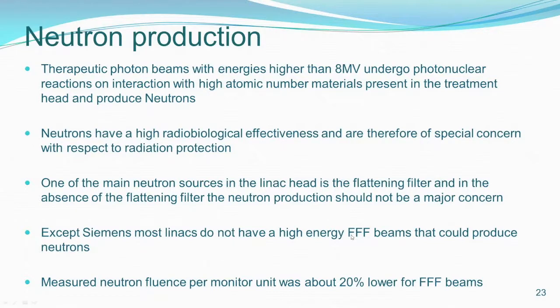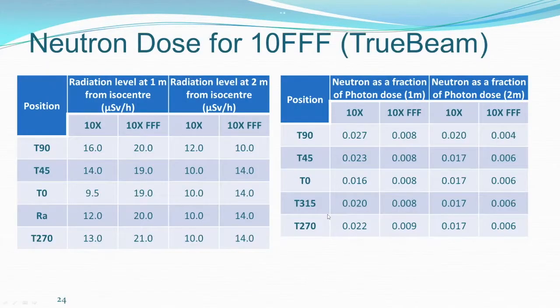And moreover, most of the LINACs that have the FFF, except Siemens, which is not in the market now, do not have very high energies with the FFF. So neutrons are not an issue even otherwise, and you don't have high energy beams where you have to worry about neutrons. And we also did some neutron measurement for 10 MV. There's something interesting which I want to share with you. For example, if you look at this, I have for 10X and 10FFF the neutron measurement, in microsievert per hour at 1 meter and 2 meter. For 10X, it is 16 microsievert. For 10FFF, it is 20 microsievert.